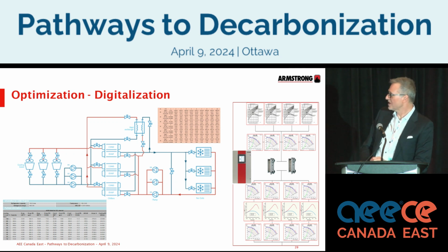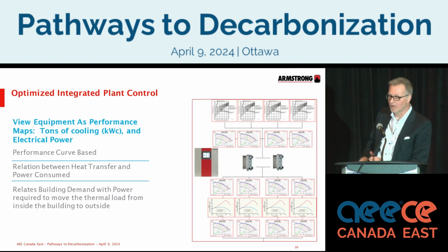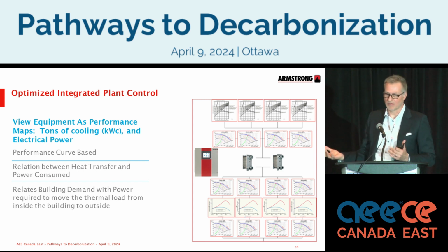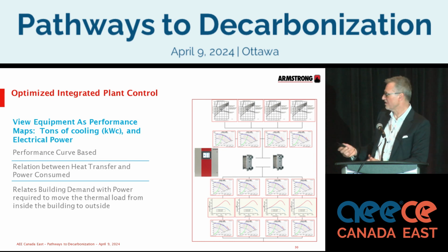What we're really doing is mapping the tons of cooling and the electrical power. That's the association. So how many tons of cooling and how much power are we consuming? It's all performance curve based. It's a relation between heat transfer and power consumed. And it relates the building demand and power required to move that thermal load from inside the building to outside. So how much power do I need to move that thermal load? That's what we're doing here.